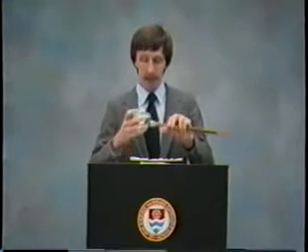The way that's done usually is with a pitot gauge. A pitot gauge senses the velocity head that's coming out of the hydrant in the flowing stream, converts that reading to a pressure reading that you can read off the face of the pressure gauge. This is traditionally the way that fire hydrant flow measurements are made.